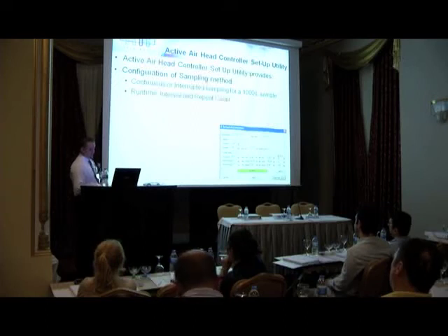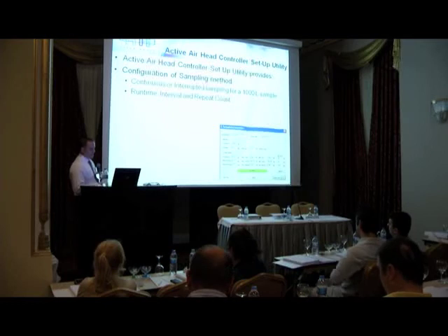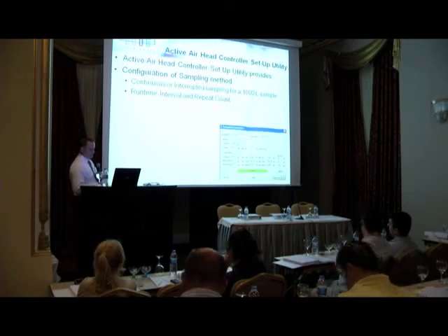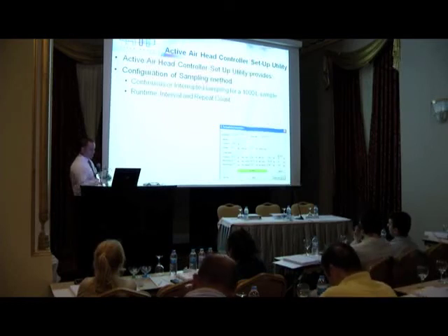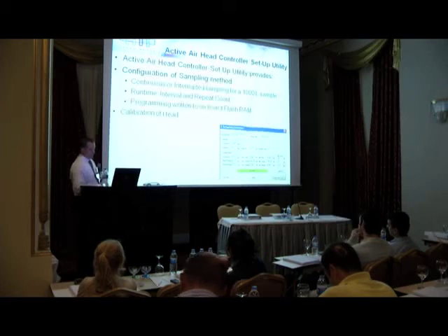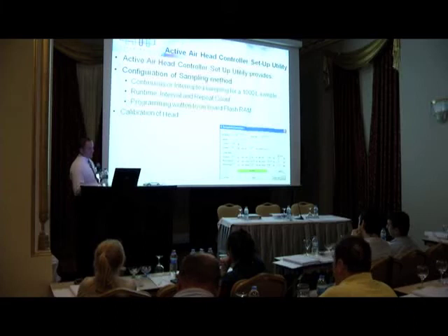So we can do that. We can say how long you want to sample for, what the interval is between sample periods, and how often you want that to repeat. So what that gives you is, say for instance, you can spread that over 2 hours or 2.5 hours of a total cycle to take place.